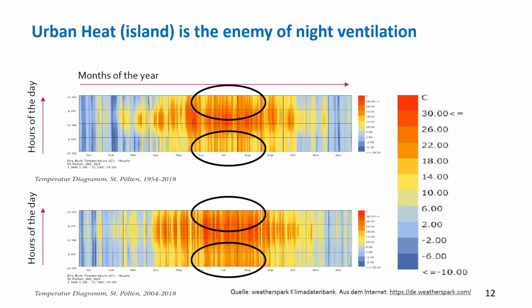To read this from left to right, there goes the year. From bottom to up, there goes the hours of the day. And just looking at the temperature scale, you can easily find out that the late evenings, which is this area, the late summer evening, just look by color how the late summer evenings have changed from statistically relevant lower than 18, or at least lower than 22, to statistically relevant never lower than 18 anymore. And sometimes, and not only sometimes, but often in the range up to 26. So you see by one glance how this late evening situation, which is very much important for the night ventilation effectiveness, has changed, and the early morning hours the same.